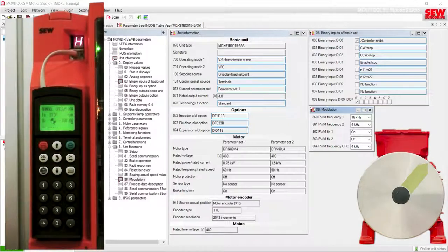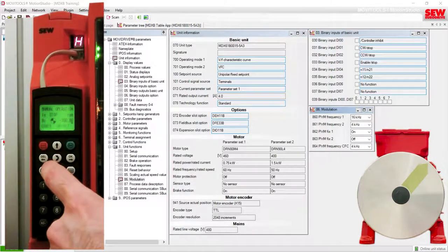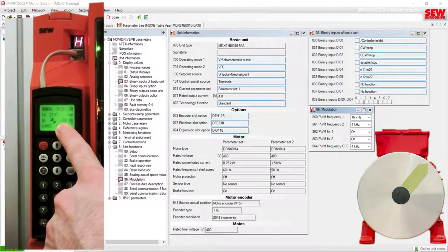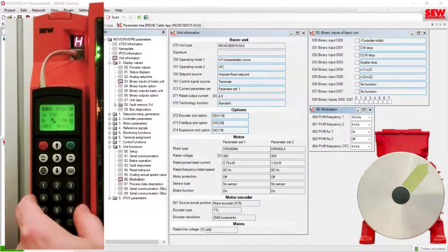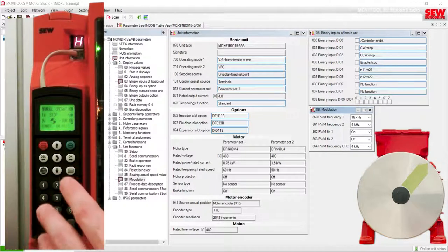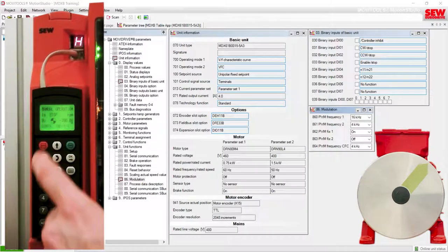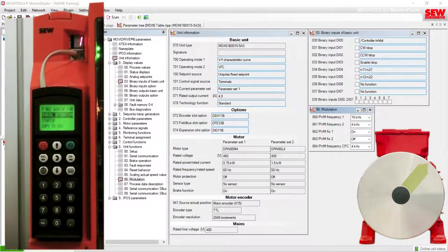To exit manual mode, first turn on controller inhibit by deactivating DI00. The display shows controller inhibit. We always need to back out of manual mode — if we leave the MOVIDRIVE in manual mode from the keypad and try to take control back with the switch box or from the fieldbus words, the motor drive will not respond because it is being controlled by the keypad. To give control back to normal operation, always make sure to exit manual mode by pressing the delete key. We are now out of manual operation.